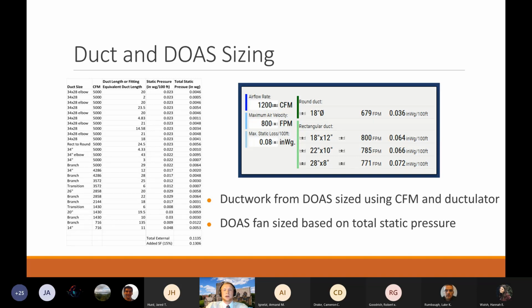We found the equivalent duct lengths and then the fitting losses along the longest duct route, and we made those calculations and we added up all those values, which you can see in the table to the left. With an additional 15% factor of safety just added in, the static pressure was 0.13 inches of water, which is within the range for the DOAS unit that we selected. So I'm going to pass it on to Rachel to talk more about our system.